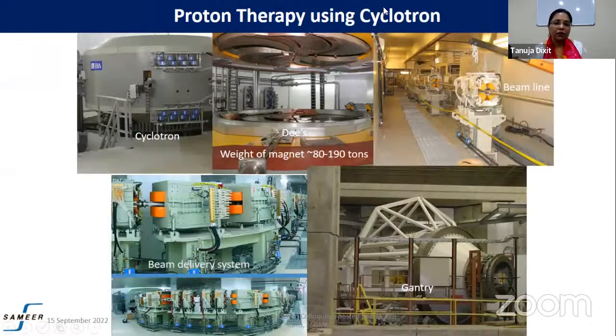This is how a cyclotron-based system looks like. This is a picture of an IBA company-based cyclotron. As explained earlier, the cyclotron consists of two magnets with the particle source placed in the center, as shown in this slide. When the protons are accelerated to the final energy, they are taken out to the beamline, and from the delivery system it goes to the gantry.